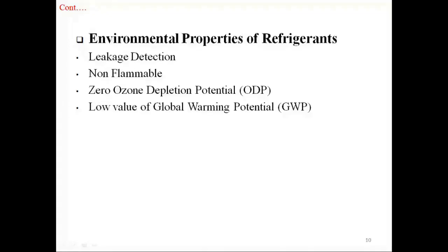Environmental properties of refrigerants. In case of leakage, refrigerants should be easily detected; otherwise strong-smelling chemicals may be added. Refrigerants should be non-flammable. Refrigerants should have a zero value of ODP (ozone depletion potential). The ODP of a refrigerant is the relative amount of depletion to the ozone layer it can cause; ODP of R11 is fixed at a maximum value of 1. Refrigerants should have a low value of GWP (global warming potential). GWP is the relative measure of how much heat a refrigerant traps in the atmosphere. GWP of carbon dioxide is 1.